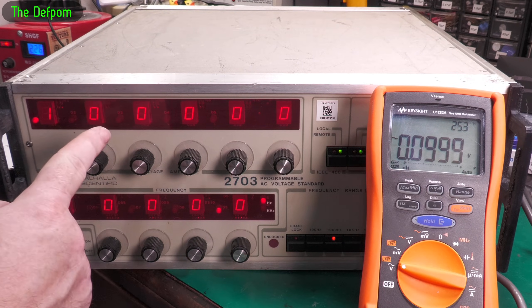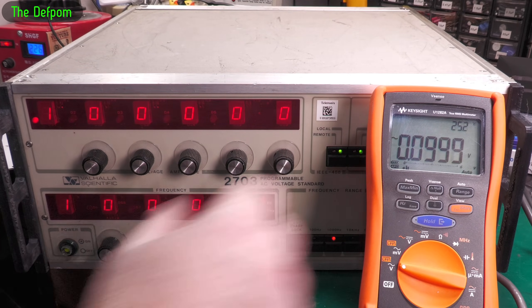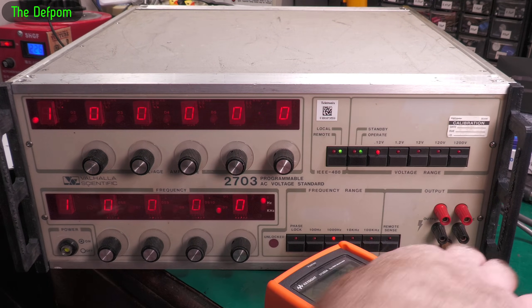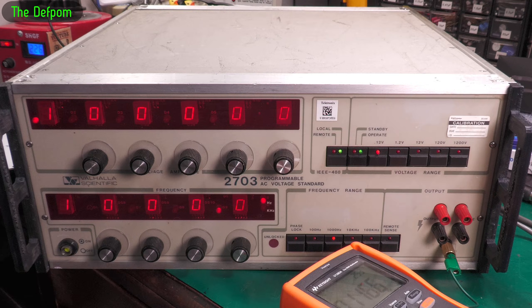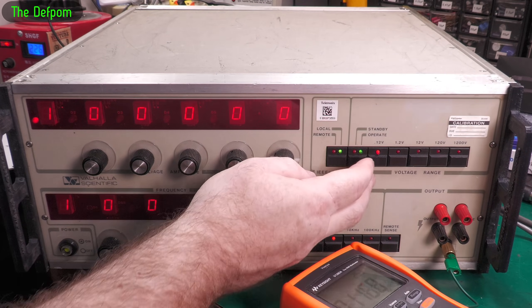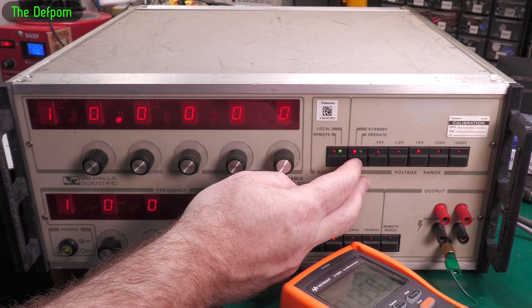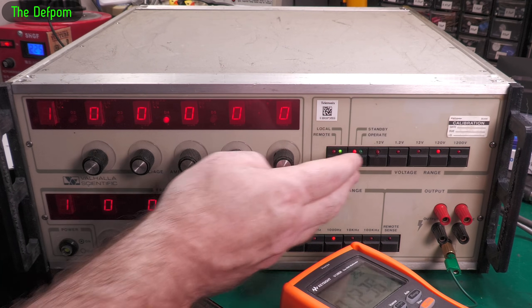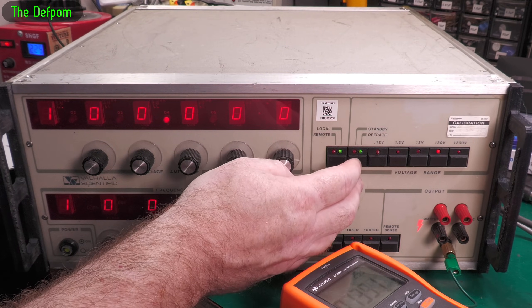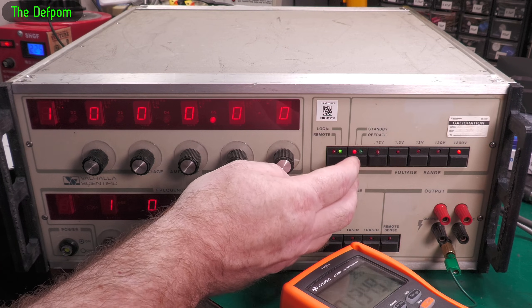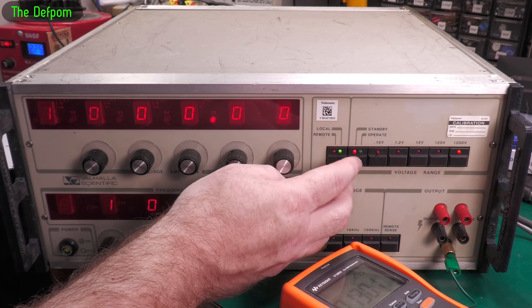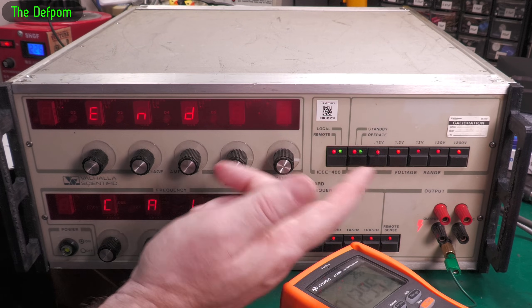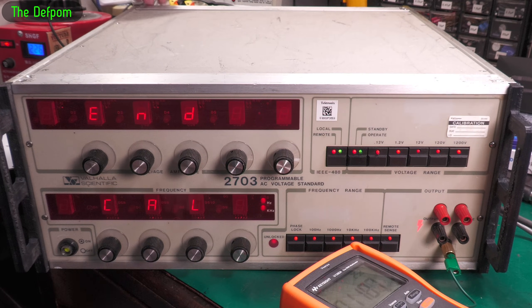So I'm not going to, this is 0.1 volts, it's there. What I'm going to do is unplug this because I don't want to shove a thousand volts out into my meter, although the Keysight can't handle it. Now I'm going to push this button to go through each step because I'm not going to change any of these settings. These ones are already done, I've already calibrated these. Although it wasn't fully warmed up, it's close. I'm not going to adjust these. So we push it, each time it changes the range, gives you a chance, then you enable the output with that. And then you finish it. Great. Now turn the calibration key off.